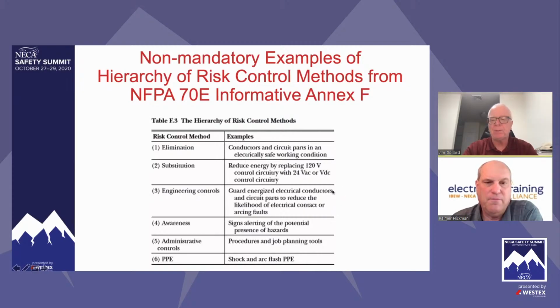Absolutely. So, if Palmer and I were working together and the task was to open a low voltage power circuit breaker and then rack it out and then go to a downstream switchboard and verify de-energization, what are we doing? We're creating an electrically safe work condition. But Palmer and I would implement engineering controls. We wouldn't put our hand on that low voltage power circuit breaker. We would use a device to remotely open that circuit breaker. And then we would use a device to remotely rack that device out. That's a very high energy area in the distribution system. And if something does go wrong, we don't want an employee standing in front of that equipment.